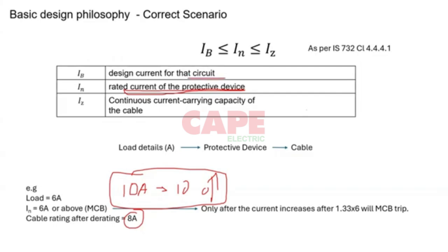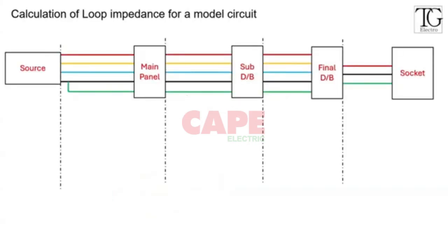So if they don't have any budget or those concerns, that is a secondary thing. But on the point of the topic, it is always better to rate the protective device to the cable. If you want, you can increase the cable size. But obviously, you can't put a much higher rating cable on a small protective device. You won't be able to fit it in the terminal. That concern is also there. So now on to the topic.